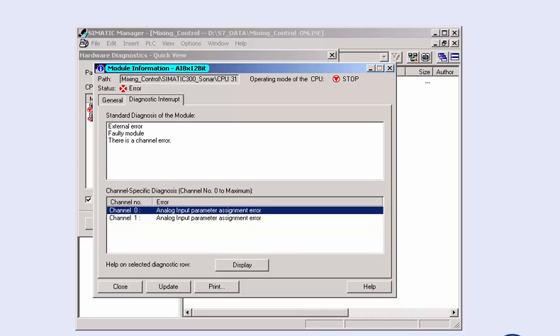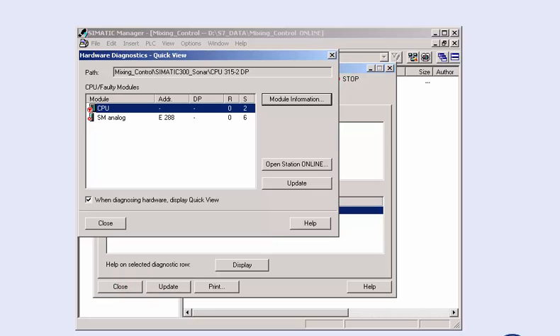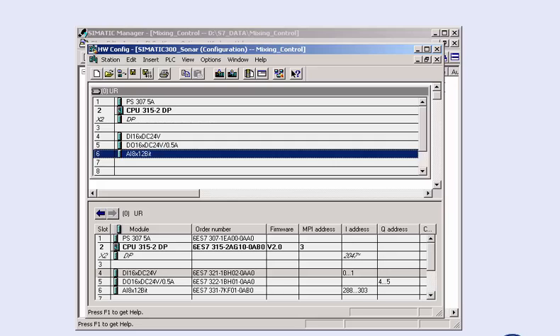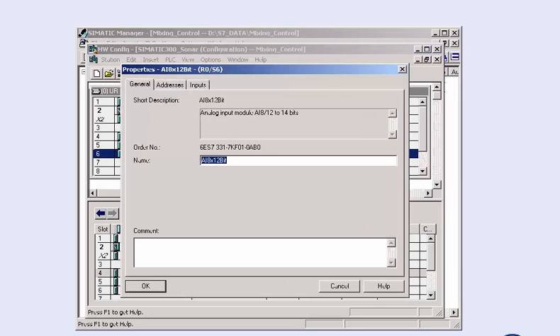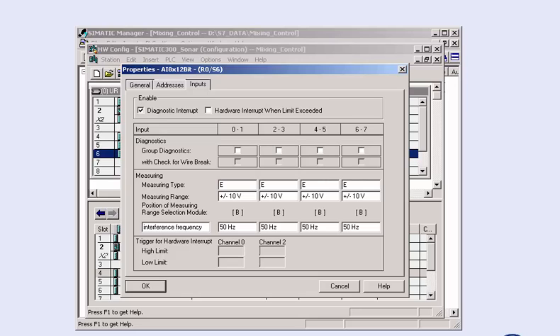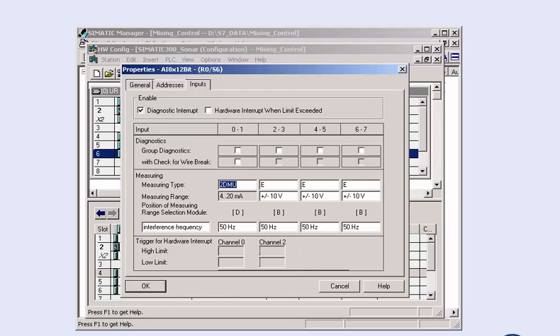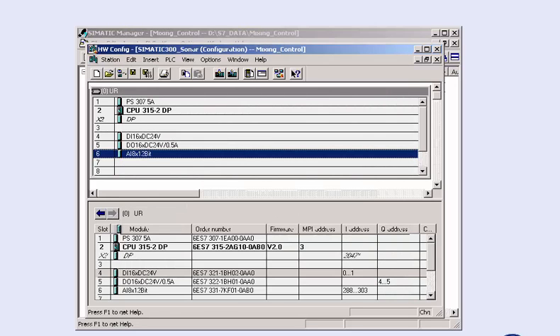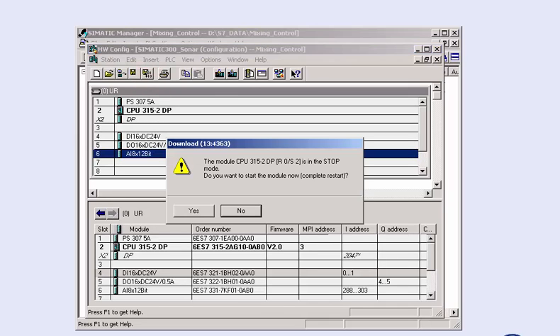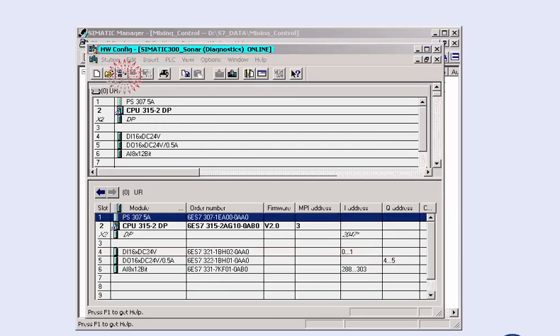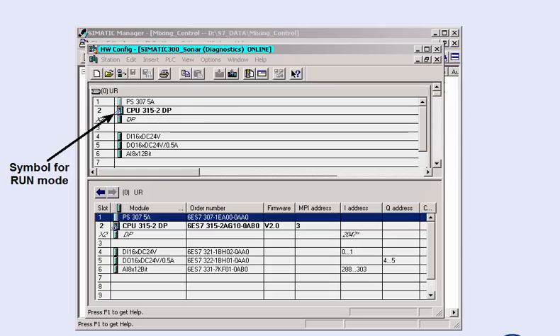From our configuration documents, we know that the connected sensor supplies a current value of 4 to 20 milliamperes. For channels 0 and 1, the measured range of plus/minus 10 volts is the wrong default setting. In the offline project, we correct the measured range, save and compile the changed configuration. Subsequently, we re-transfer the configuration and start the CPU. The CPU remains in run mode and there is no longer a diagnostic interrupt.